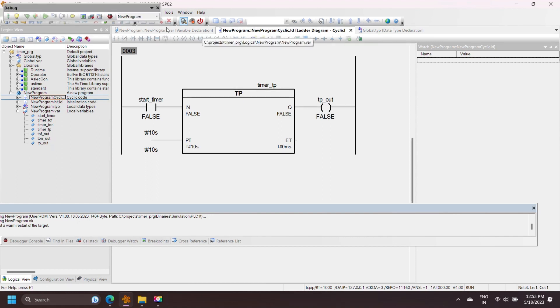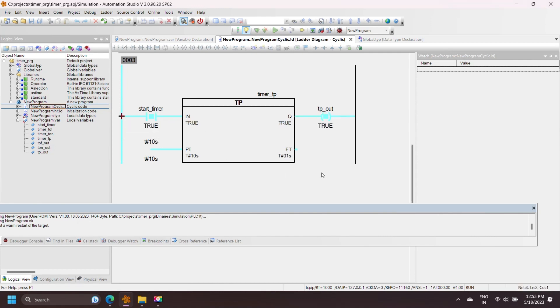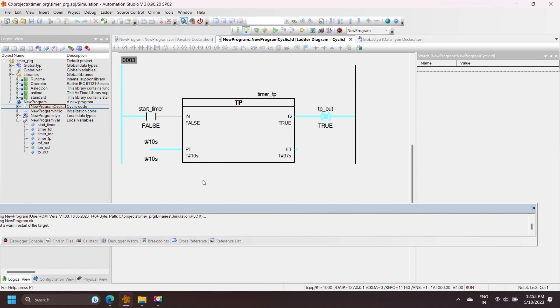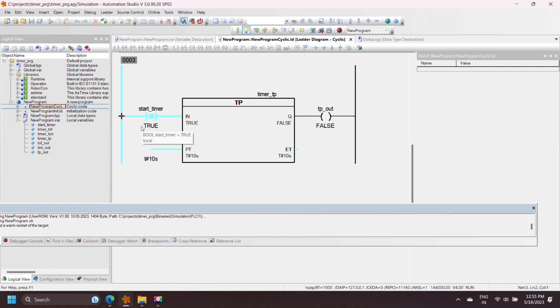In this pulse timer (TP) example, if the input of the timer is set to true, then timer operation starts, timer output is set to true, and elapsed time increments. During the operation of the pulse timer, any changes in the timer input have no effect on elapsed time or timer output. Once the timer elapsed time equals the timer preset value, timer operation stops and timer output is set to false.